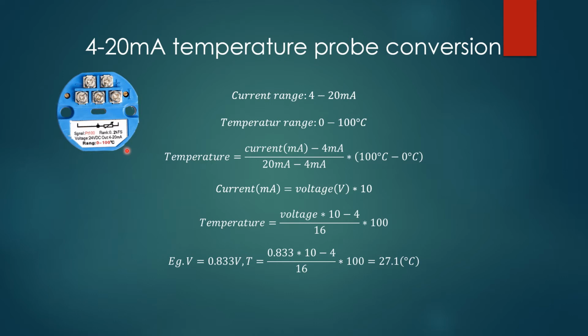So let's see how to get the temperature back once we read the current. The current has this range, 4 to 20 milliamps, and temperature has this other range, 0 to 100 degrees C. If you take the current readout and subtract the 4, because 4 is the starting point, and then divide by the range, 20 minus 4, a 16 milliamp range, how far along the range you are is calculated in this fraction. Then you want to recast that into the temperature range, which is the high temperature 100 minus the low temperature 0, and you multiply these together.